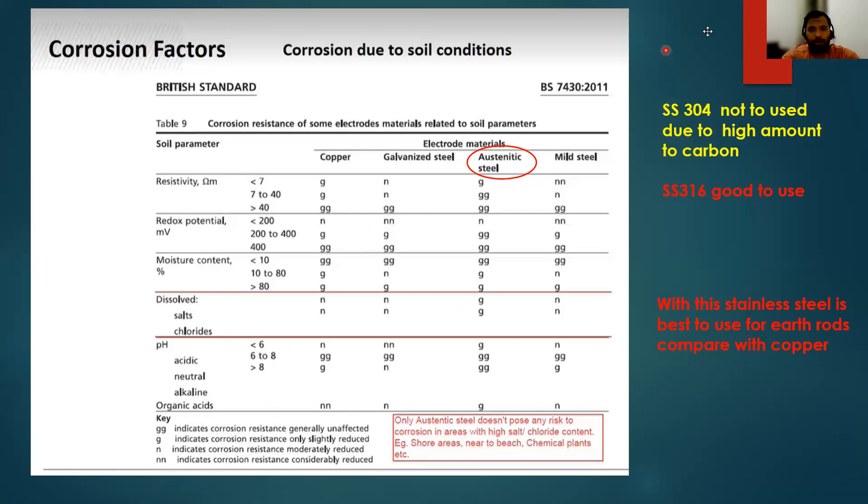Austenitic steel is nothing but stainless steel. Stainless steel, you have different types of grades. Mostly a few suppliers are using SS304. It should not be used because it has high carbon content. If there is high carbon content, then it will not show these values. You have to use SS316. It is a very good material.